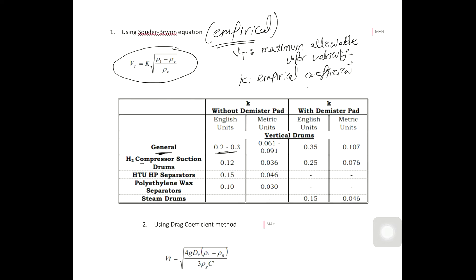If this vertical separator is used on the suction of a compressor, you will be more conservative. Especially for the suction of compressors or any expensive equipment in the plant, you should go to computational fluid dynamics to test your design. But normally, in general service, you don't need CFD to test your design. We will normally take K as a general service value.